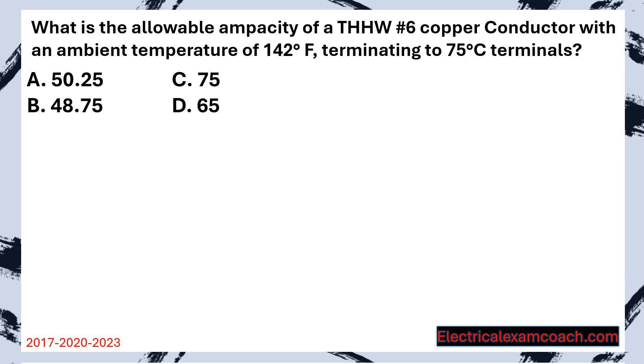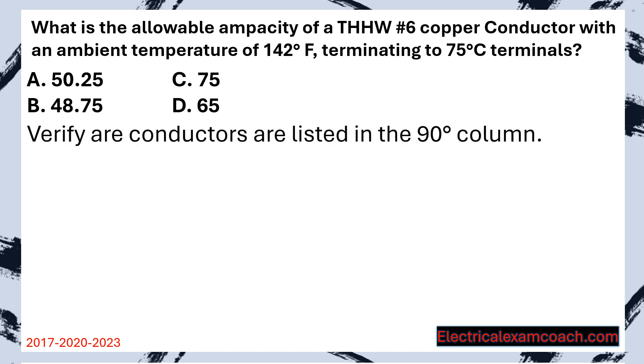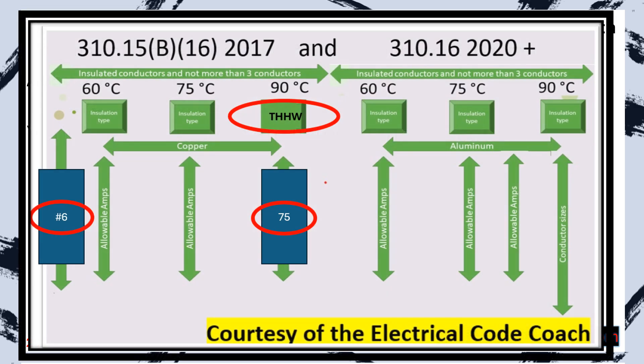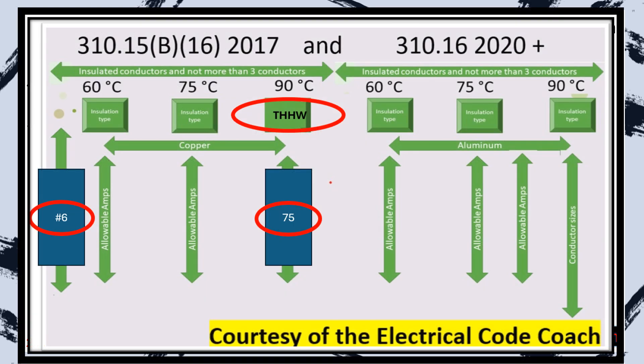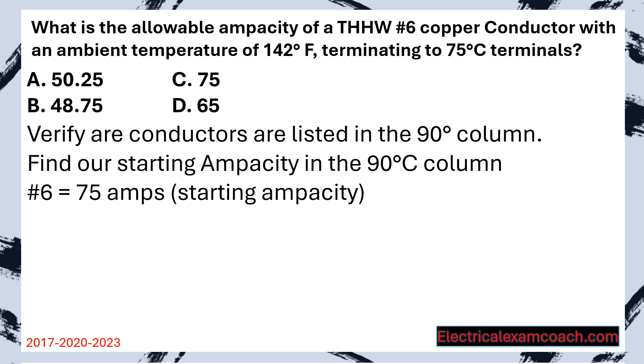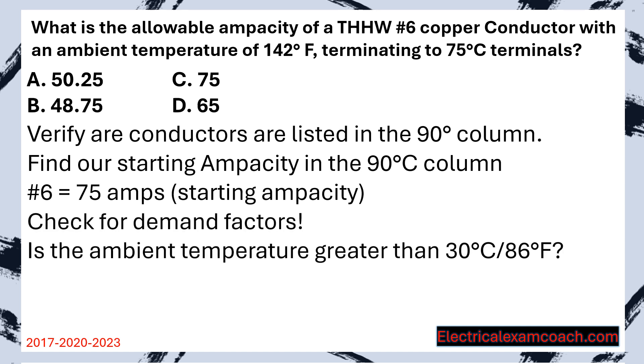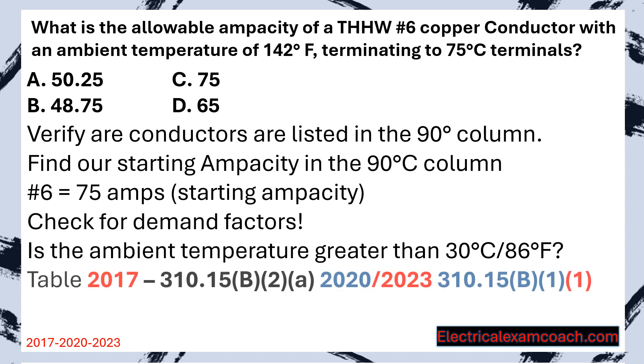Practice problem: What is the allowable ampacity of a THHW No. 6 copper conductor with an ambient temperature of 142 degrees Fahrenheit, terminating to 75 degrees C terminals? Step 1, verify the conductor is listed in the 90 degrees C column — head to the table, look for THHW, and sure enough it's there. Now find the starting ampacity in the 90 degrees C column: find No. 6, cross over, and the ampacity is 75 amps. Now check for demand factors — is the ambient temperature greater than 86 degrees Fahrenheit? It is, so there will be a demand factor.